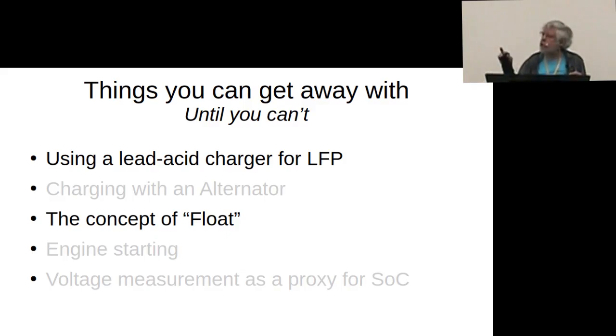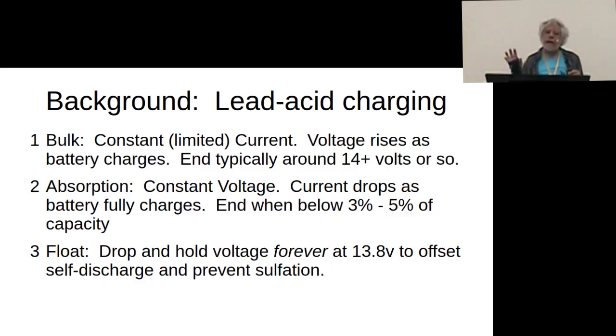In terms of charging and the concept of float, they kind of work together. Some background on how lead acid works: you start putting current into the battery, you want to limit the current, but generally the battery will start limiting the current for you - it's got a lot of internal resistance - until you get up to 14, 15 volts, somewhere in there. It's not critical. You push the voltage up, then hold it there for absorption, letting all the juice absorb into the battery until the current drops. When it drops down to about 3 or 5% capacity, you're done charging.